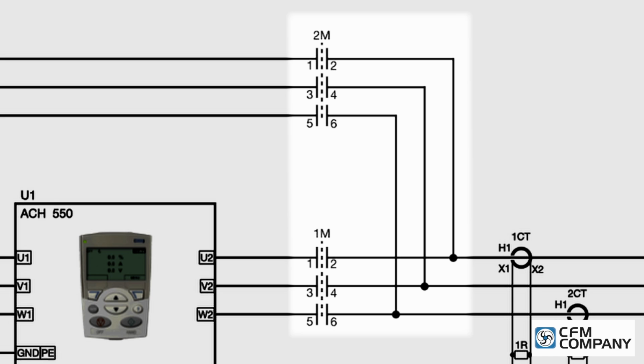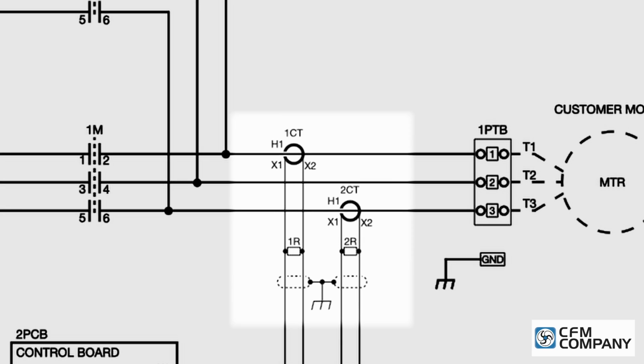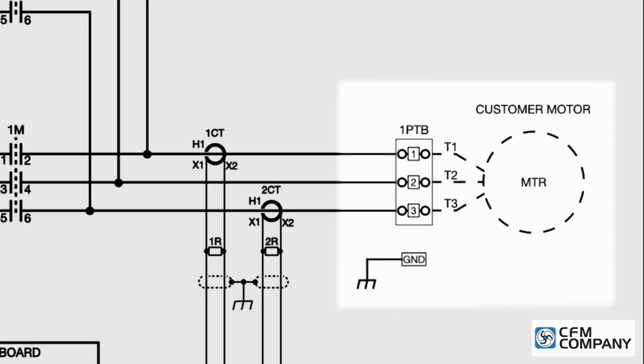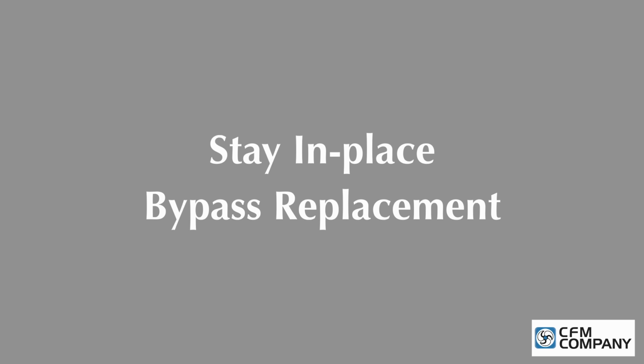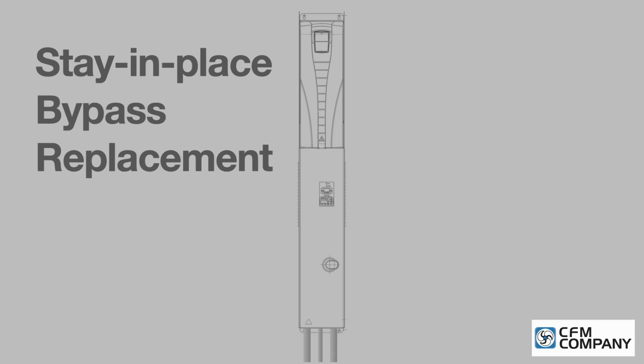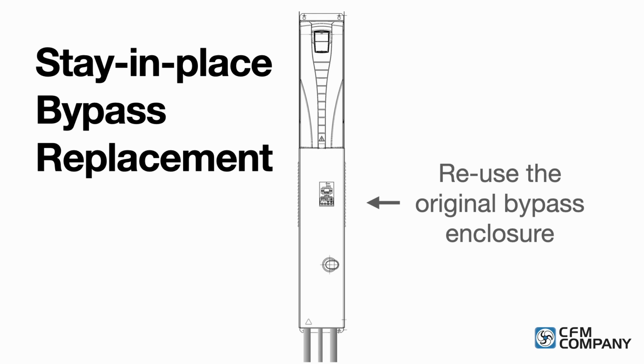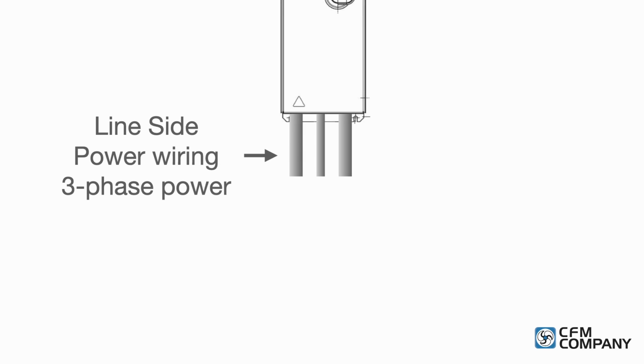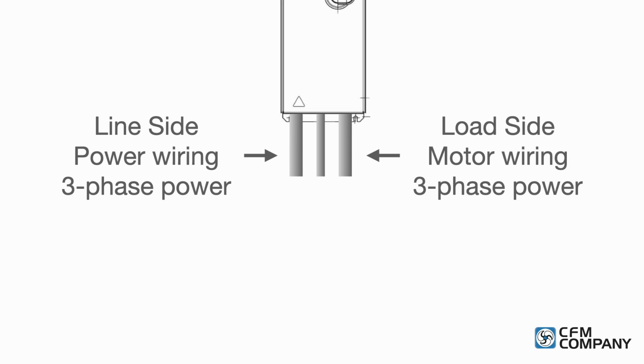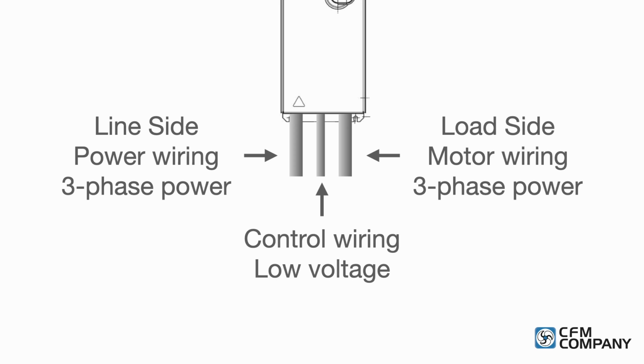The output of the bypass and drive contactors is wired through the two current transducers. Then the output wires land on the motor terminal block. The customer connects the motor leads to the motor terminal block. The advantage of reusing the original bypass enclosure is that the conduit connection for the three-phase line wires, the conduit connection for the three-phase motor wires, and the conduit connection for the building automation controls can stay in place. This makes it possible to complete the retrofit in a few hours with minimal changes to the original hard-piped electrical connections.